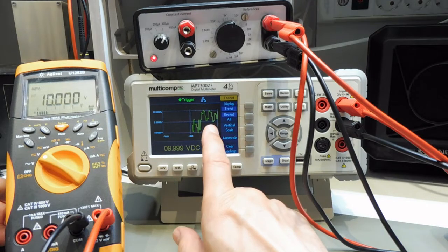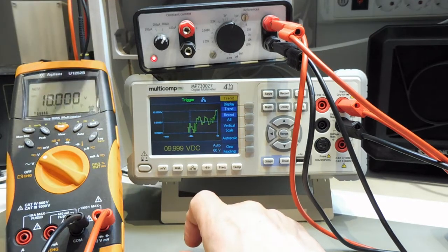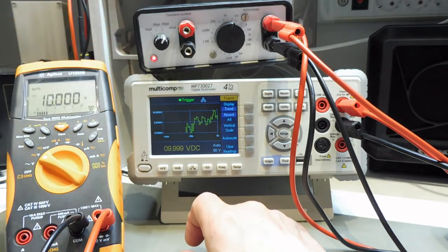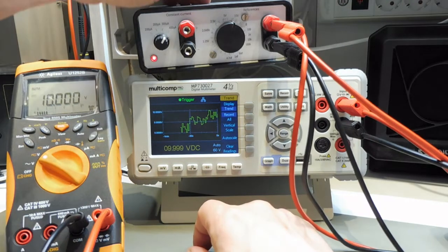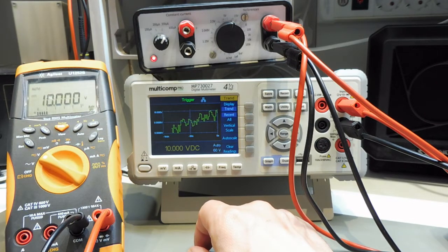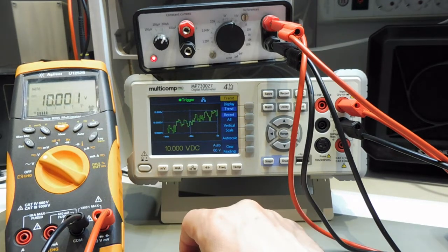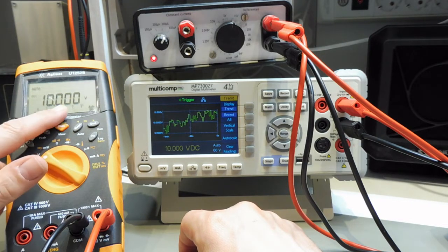So if you let it run for 1 hour, with the reference in this meter here and the reference here in this meter, you can probably see all of the temperature changes here in my room. I can even change the voltages here if I just physically move the meter. That's enough to have little minute changes, and you can see them here in the data. That's something that you will not easily observe when you just look at the numbers here.